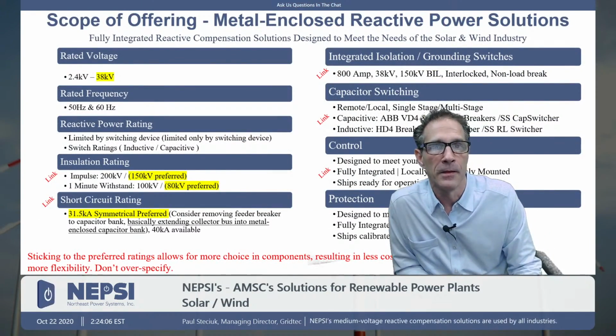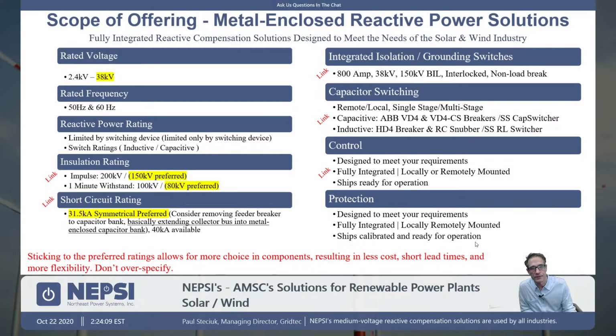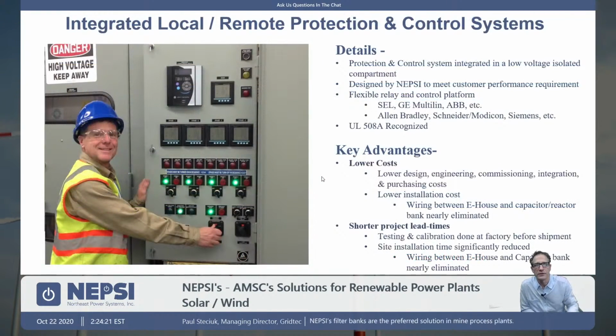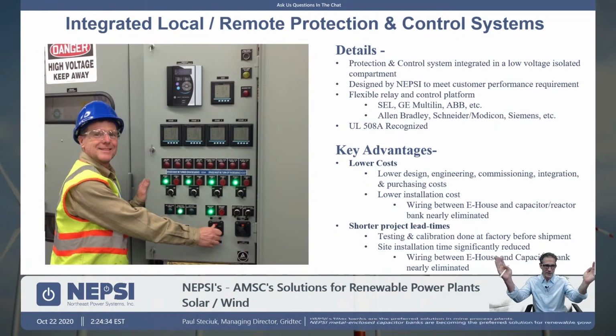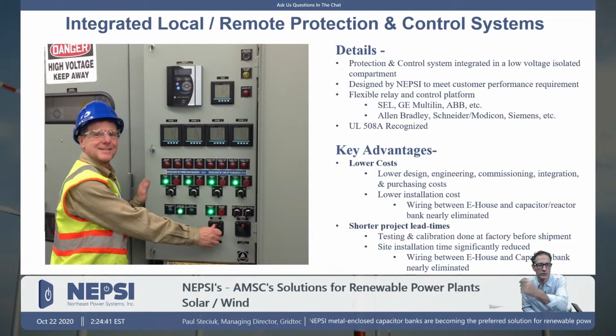So capacitor switching, we talked about that already, the choices you have between the breakers, and we're going to show some pictures of that. The control and protection is something else that's interesting. For most projects we see that the customer, well, the developer or the engineering firm involved with the equipment will put the control and protection system into the e-house.